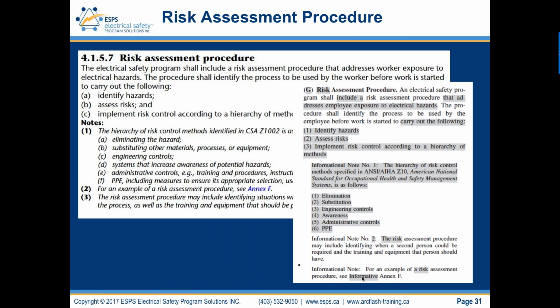So the risk assessment procedure: these are the two clauses in Z462 on the left and 70E on the right. They're identical, they're harmonized. They will point to Canadian and US standards. So you'll notice it says CSA Z1002 for the hierarchy of controls and ANSI Z10 for the hierarchy of controls. And the hierarchy of controls is what we're going to apply to the inherent or initial risk level that will be unacceptable to achieve a residual risk level that will be as low as reasonably practicable.